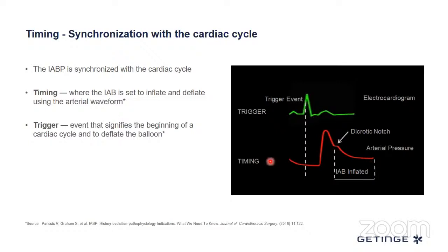We can get it in two ways. One is the more traditional way, a conventional balloon connected to a disposable transducer, like a fluid-based pressure reading, or we can get it through fiber optic, which doesn't require a transducer. That's very fast and very accurate, and it's even immune to electrosurgical interference.